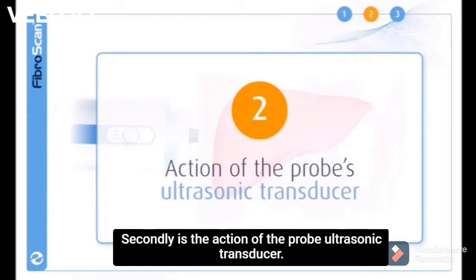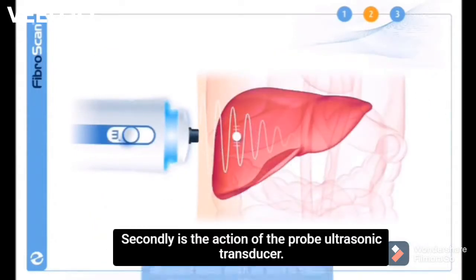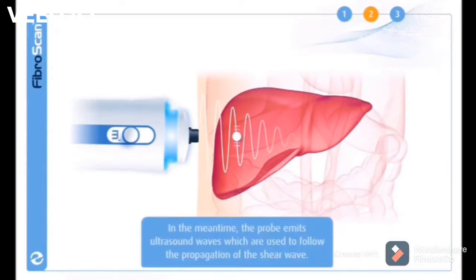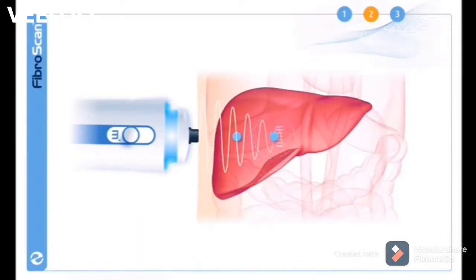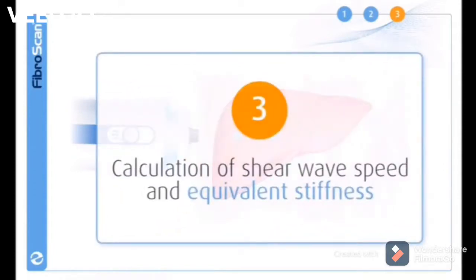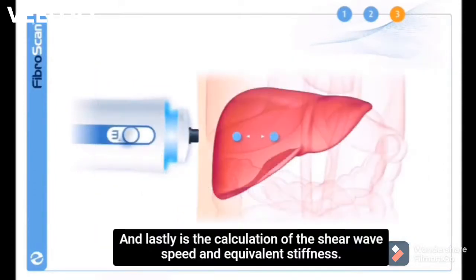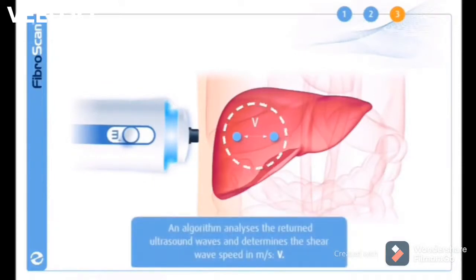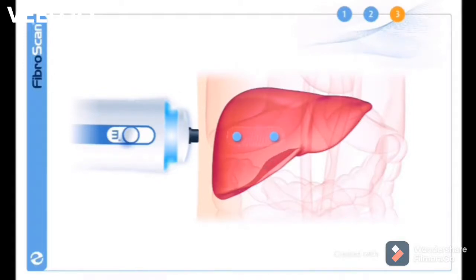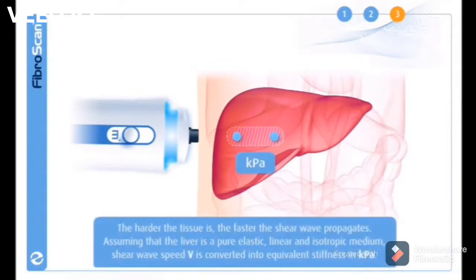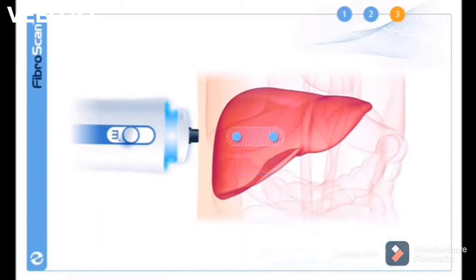Secondly is the action of the probe's ultrasonic transducer. In the meantime, the probe emits ultrasound waves which are used to follow the propagation of the shear wave. And lastly is the calculation of the shear wave speed and equivalent stiffness. An algorithm analyzes the returned ultrasound waves and determines the shear wave speed in meters per second, which is also known as V. The harder the tissue is, the faster the shear wave propagates, assuming that the liver is a pure elastic, linear and isotropic medium. Shear wave speed, V, is converted into equivalent stiffness in kPa.